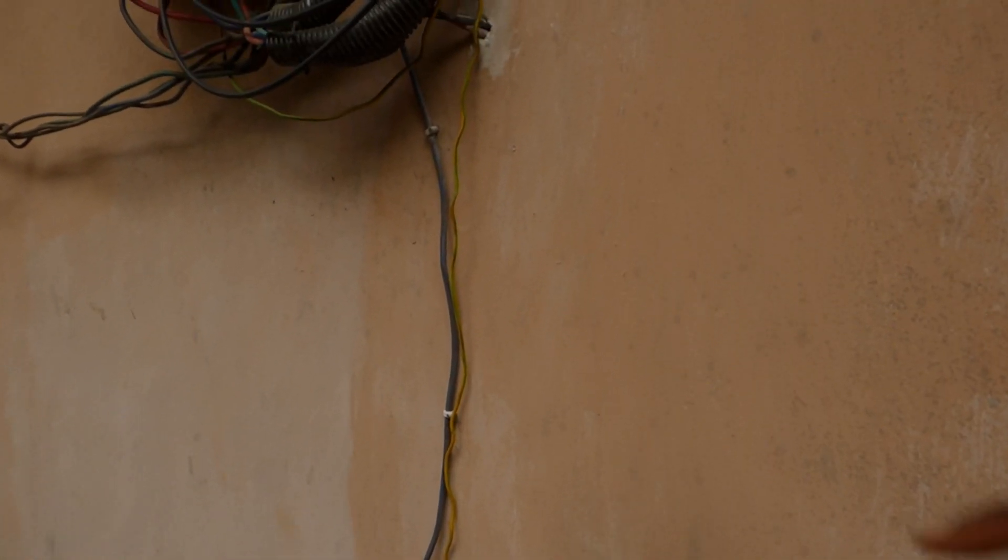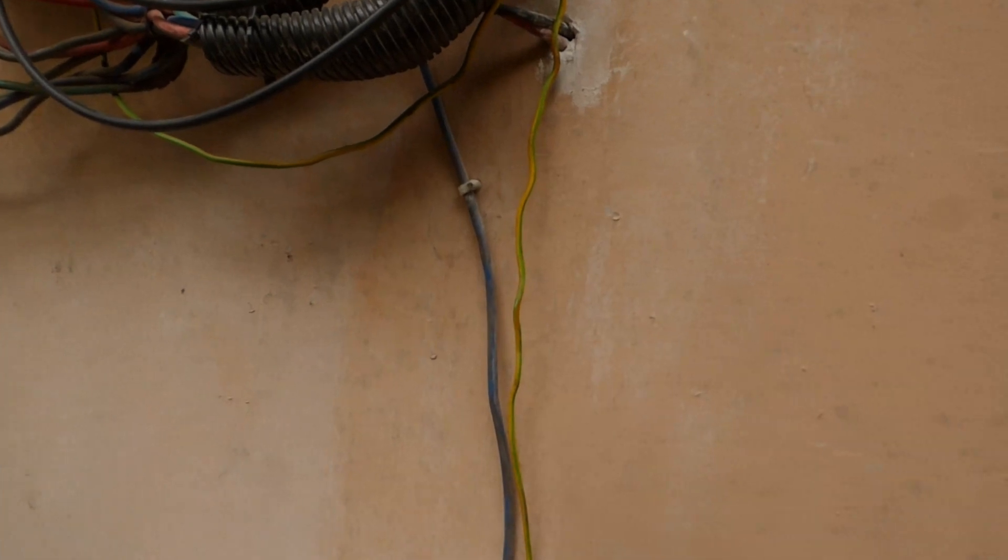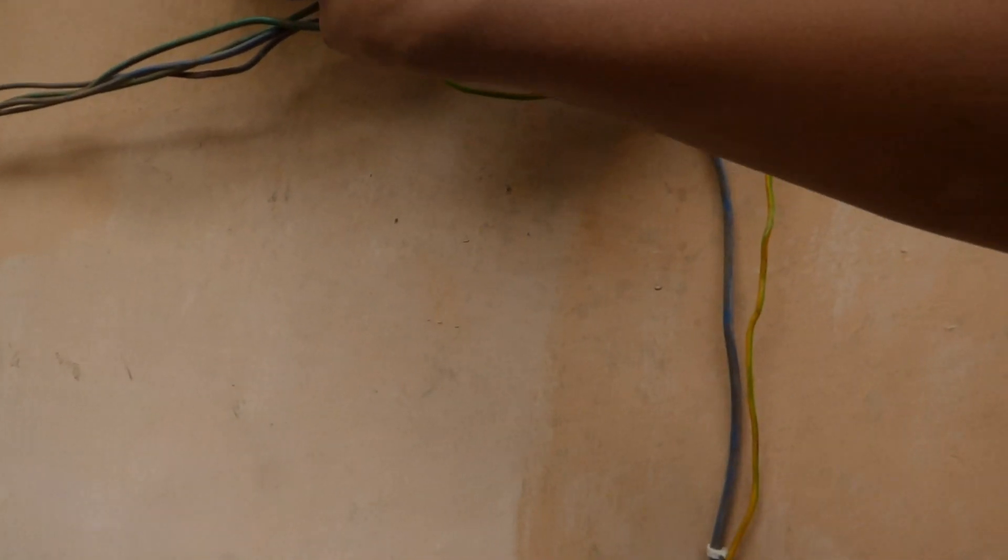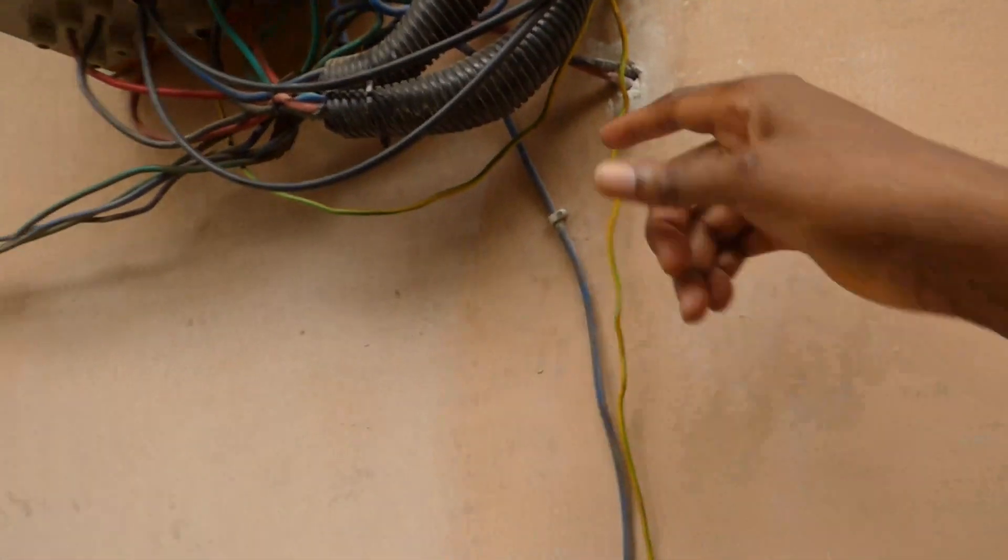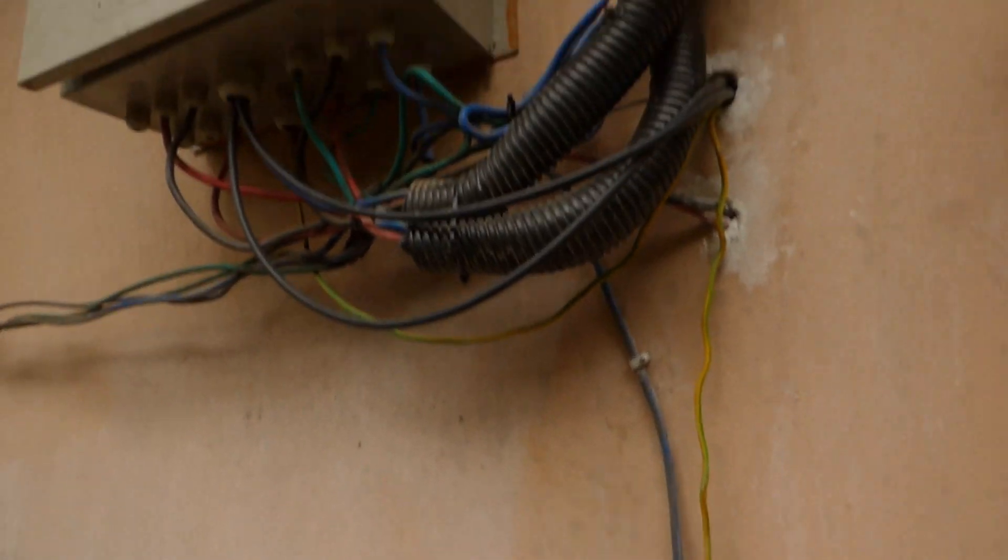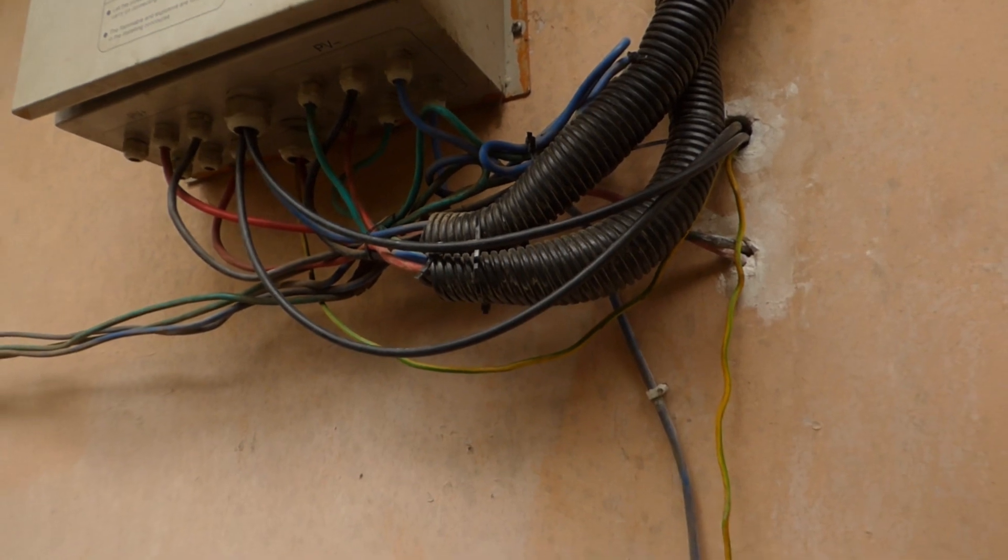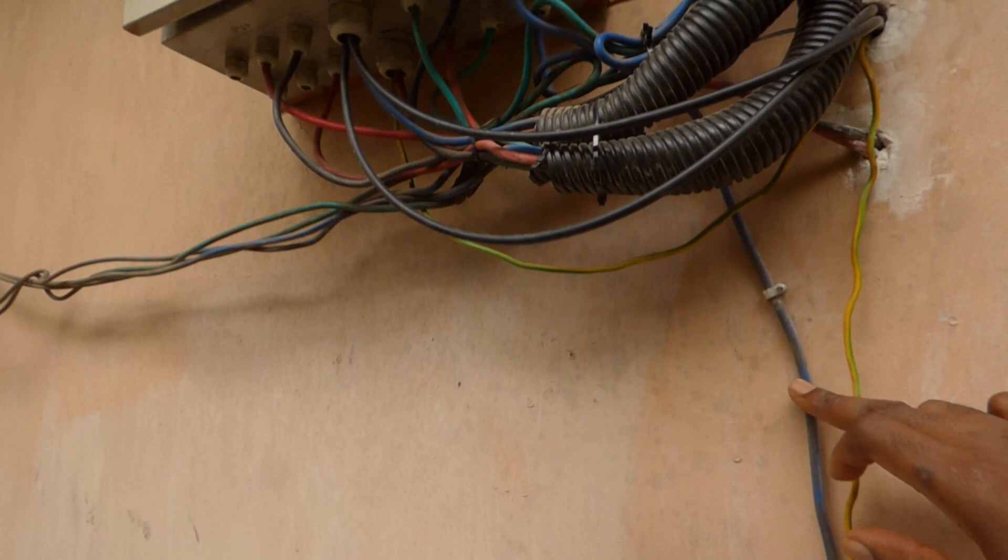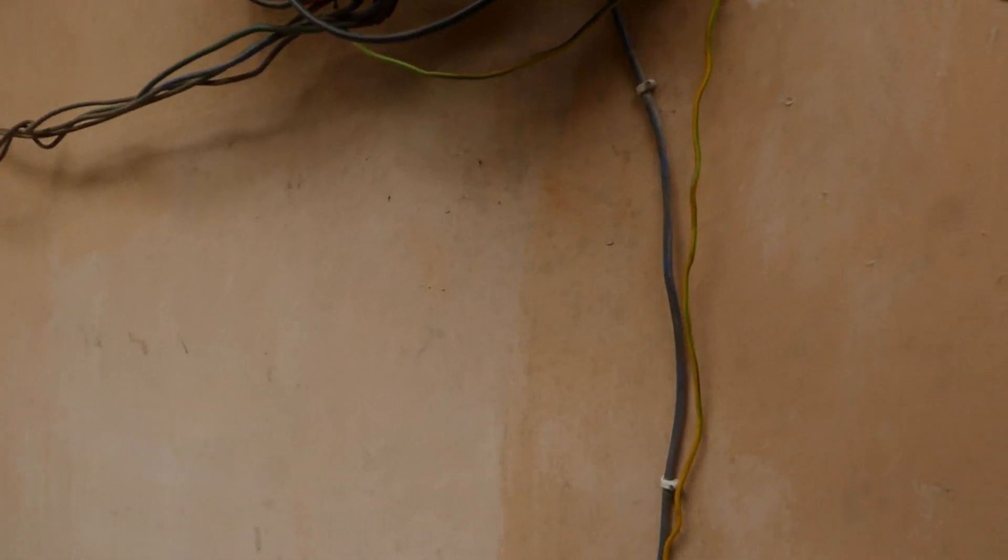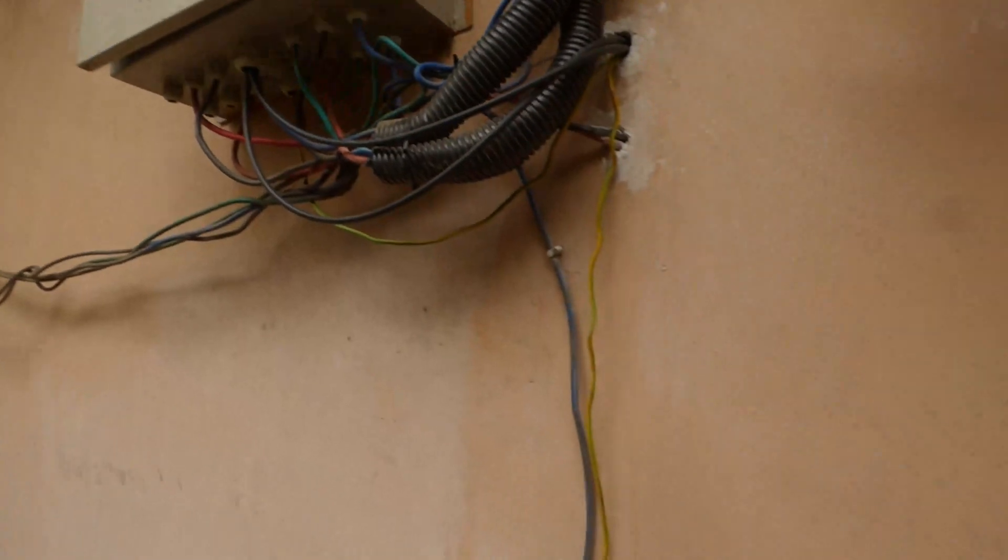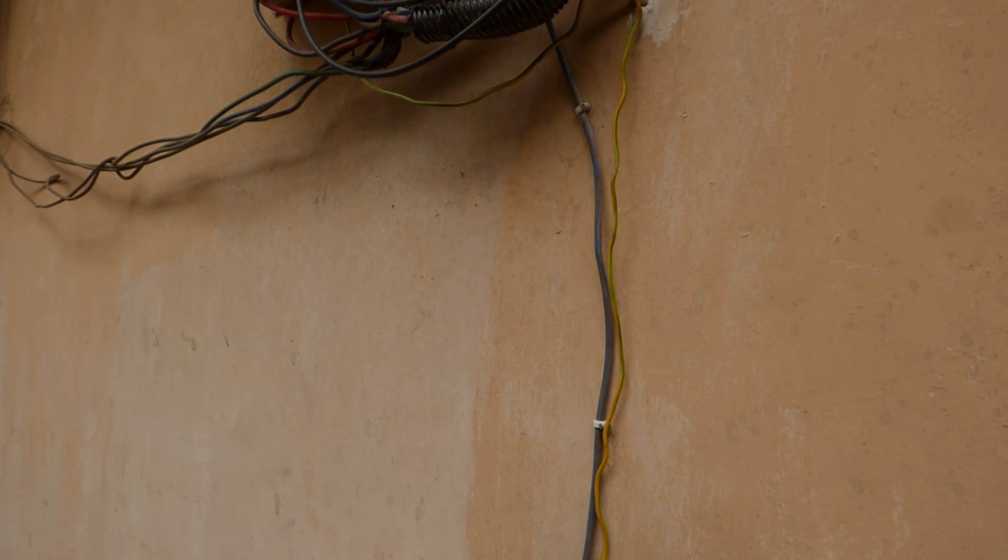So I'm back. As you see, I ran these yesterday - these are new cables to work for the Luxpower. They're PV cables, so you could see obviously superior to what we had before. This is a ground cable coming from for the chassis or anything that's metal. It's connected to the back of this, to the side here. And then the ground earth cable, which we didn't do right because it should be exposed, is connected here. So we're getting a common connection from the combiner box into everything in there.